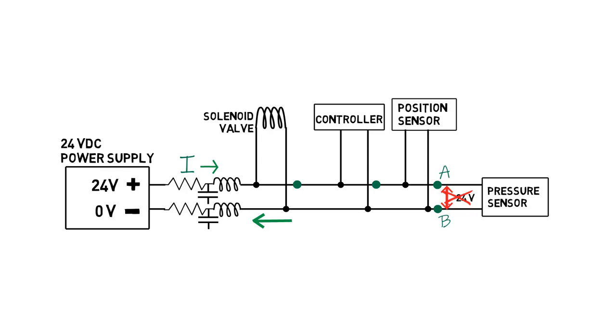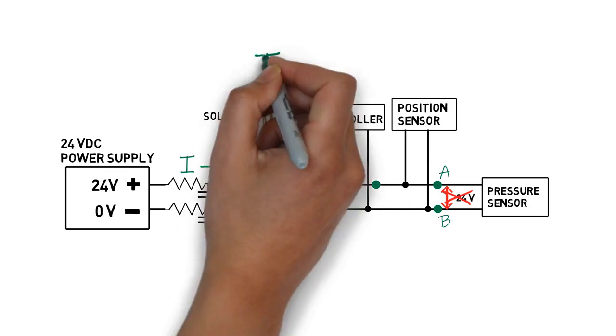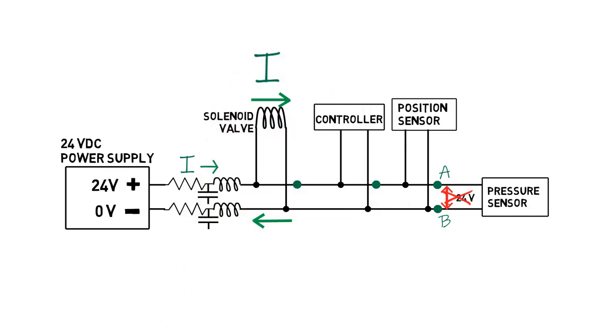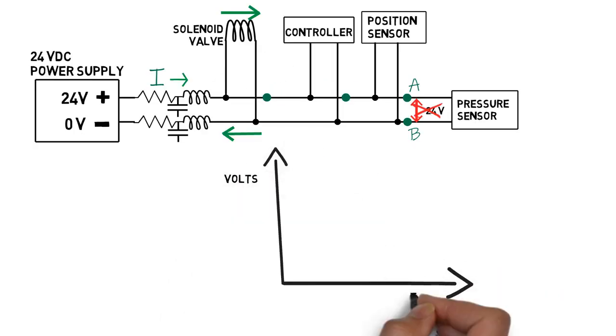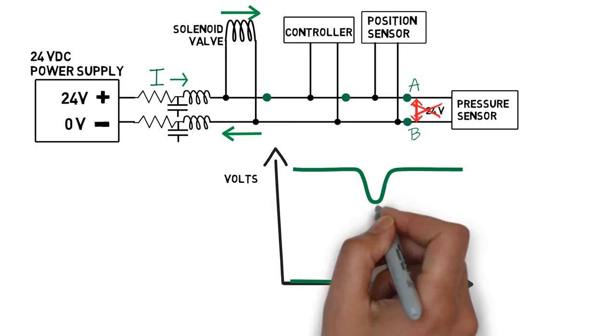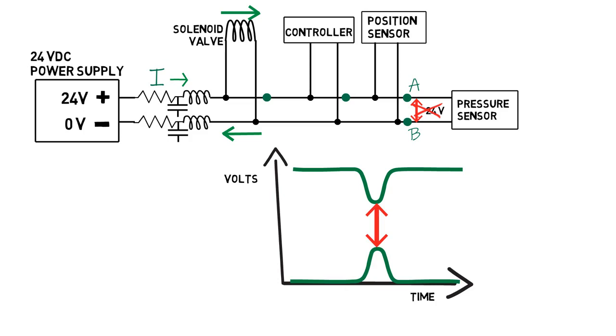This is especially pronounced when the valve fires, since solenoid valves typically draw a lot of current quickly. With a large sudden current, the plus wire voltage will dip down, and the return wire voltage will bounce up. If the resulting voltage difference is less than the required voltage of the other devices on the circuit, they may momentarily lose power.